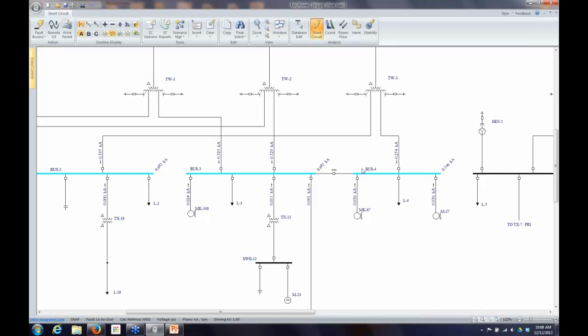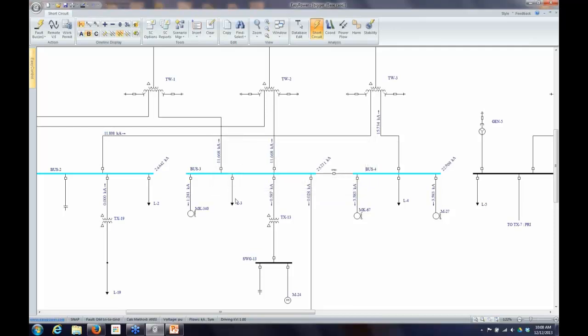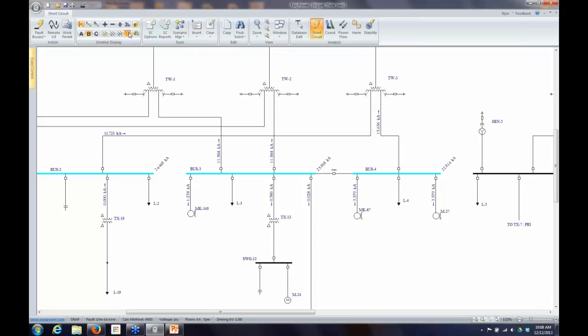The reason the line-to-ground values are very low is because we have resistance grounding on the neutrals. The double line-to-ground option changes what's being displayed to B or C phase, and you'll see some interesting results based on the direction of currents. The final option is the line-to-line fault. I'll go back to three-phase.